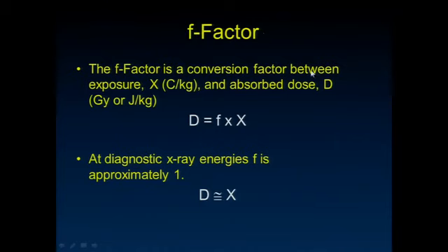If I look at the conversion factor between exposure, which is charge per kilogram, and absorbed dose, the same thing is true. Really at diagnostic X-ray energies, that conversion factor, that F, is approximately 1. So if you tell me what the exposure was, I can usually say that's roughly going to be equal to what the absorbed dose is.